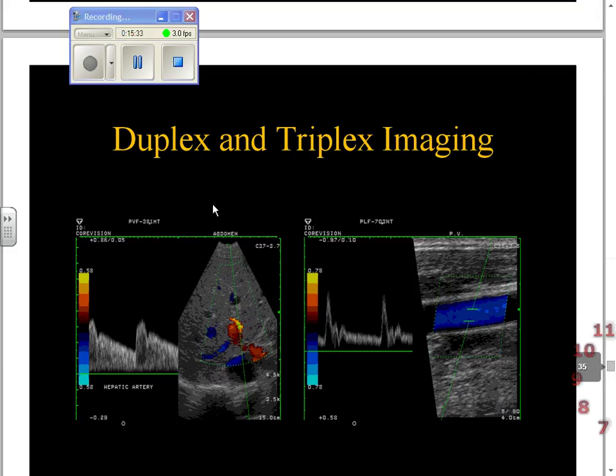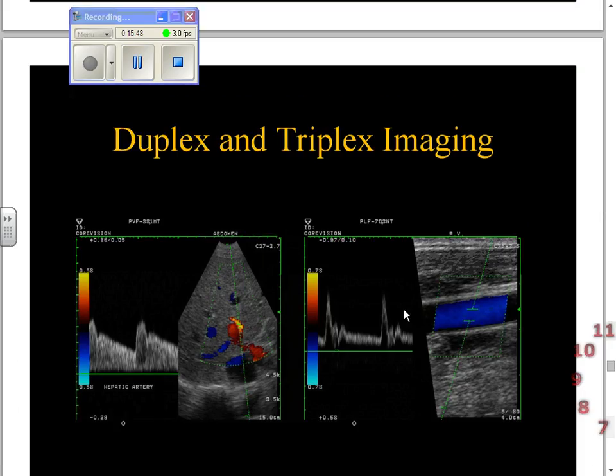This duplex and triplex means that not only do you have the picture, but you've also got graphs which show what's going on with the flow of materials through the body. Duplex is actually moving two ways. What it is, is a split screen image. It's referring to the amount of information on the screen, the way it's monitored. So you can see you've got a graph, which is the flow of blood shown graphically, and the flow of blood shown in the Doppler ultrasound image.